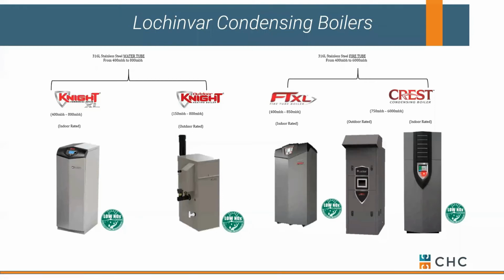If you want to go condensing, that's certainly an option too. There are no minimum return temperatures. You've got a lot of feature-rich products here, a lot of advanced controls when you go to a condensing boiler. For me, just make sure that you're taking advantage of the efficiency, and you do that with low return temperatures.